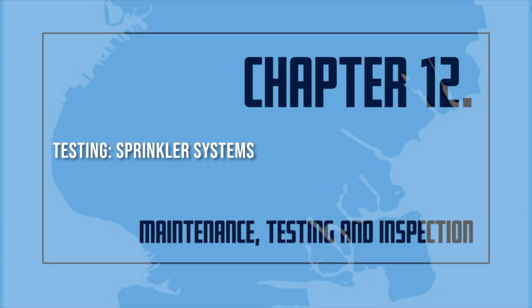Main drains. The test shall be conducted annually at each water-based fire protection system riser to determine whether there has been a change in the condition of the water supply, piping, and control valves. Antifreeze solution. The freezing point of solutions in antifreeze shall be tested annually by measuring the specific gravity with a hydrometer or refractometer and adjusting solutions if necessary. Antifreeze concentrations of glycerin shall not exceed 50%, and if propylene glycol, not exceed 40%.